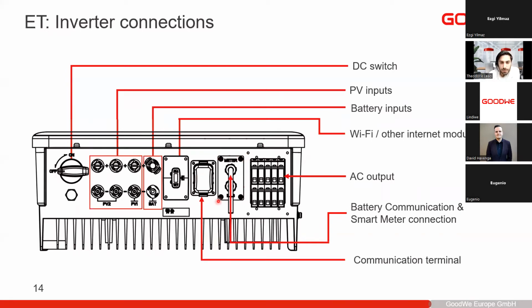After this, you see a plate with two cables coming out, already pre-wired. The first cable says meter — this goes to the smart meter that you will need to install. The second cable on the bottom side is the BMS, which goes to the battery for communication and interface with the battery.